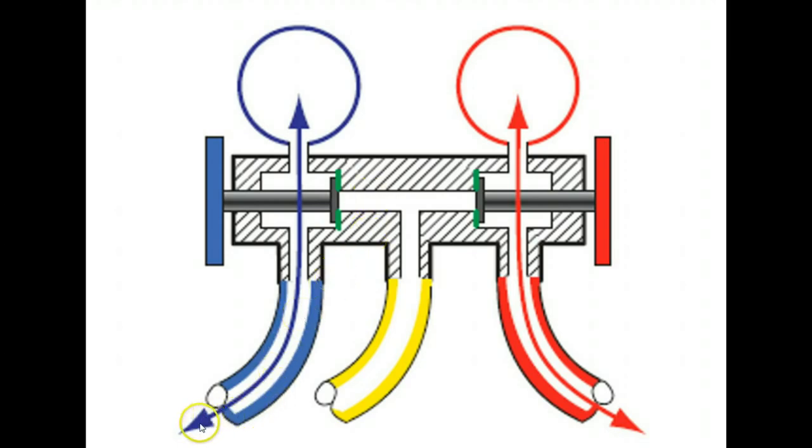Let's take a look at this. The thing to remember here is both the low and the high side hoses are always a straight through connection to the gauges. You will always measure whatever pressure is on this hose in this gauge. It doesn't matter whether these valves are open all the way or closed or in any position. These gauges always are connected to these hoses.